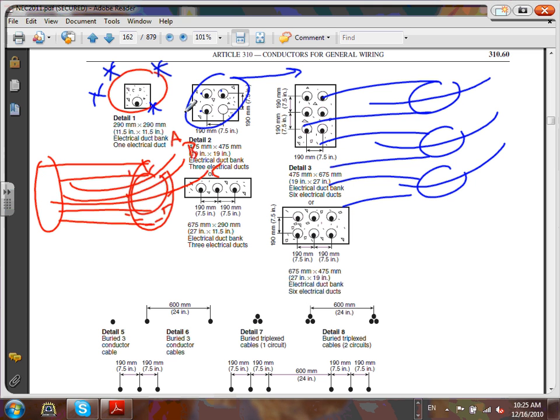But then if I can bury them, like this, direct buried cables or direct buried conductors, then you go to a different table. So all these tables that you guys can see, 310-79 and 80, they are all based on different types of underground ducts, and almost all of them are underground, because when you bring the high voltage, you bring it underground. The safest way of bringing it. Look at this detail. This detail can bring you 6 multi-conductor cable circuits, or you can apply it for 2 circuits. Here's 1 circuit here, phase A, phase B, phase C, phase A, phase B, phase C, 2 circuits.